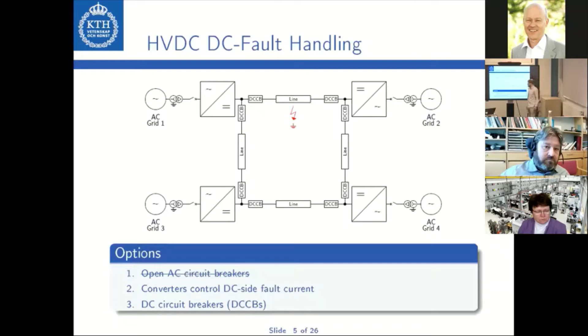Let's say this point-to-point link is expanded into a radial grid configuration. If one would now apply the first option for fault handling, one would also need to open the AC circuit breaker of this third converter. This means that the power flow on this healthy line is also interrupted, and hence this leads to unnecessary power outages. If the grid is further expanded into a ring configuration, the power level of the grid also increases. At some point, the grid becomes really large.